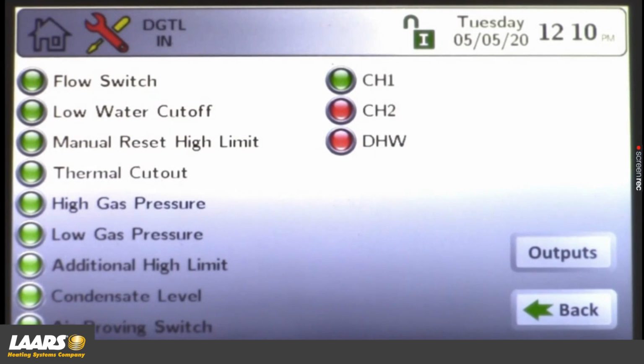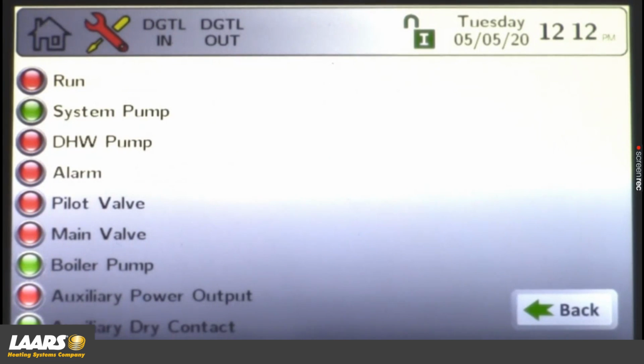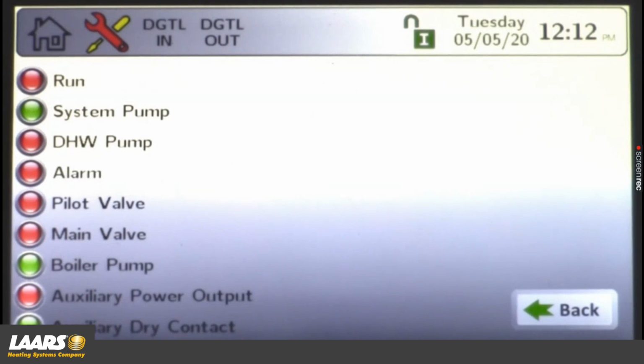That is everything in the safety chain. Again, you'll see messaging, or you can come here to Digital I/O. We also have the option here for outputs, so we can click on outputs, and it'll give us more information about the system. Right now, we're not running. Why? Because I don't have a call for heat or a TT call. But our system pump's on, DHW pump's off, we're not in an alarm status, and our boiler pump is on. As I give the boiler a call for heat, it'll go through its sequence of operation, pre-purge, ignition, etc. So that is more valuable information as well.